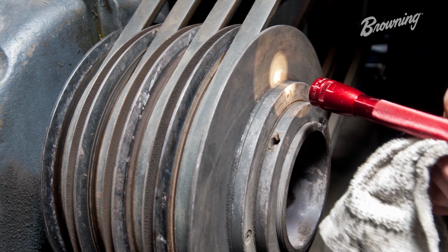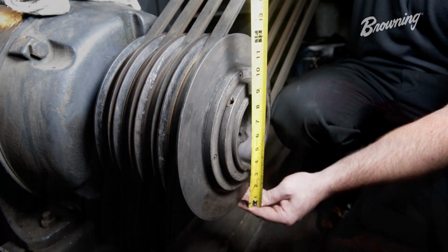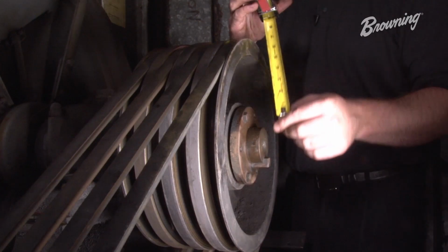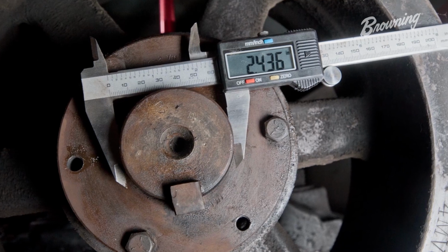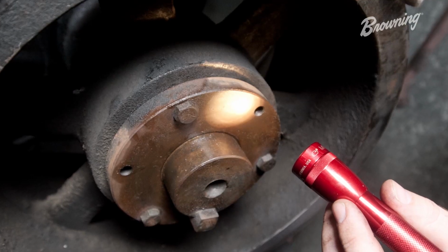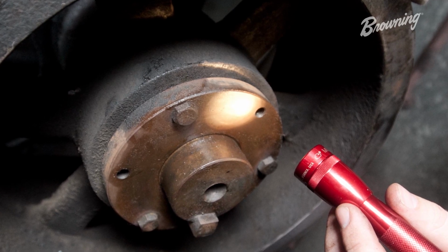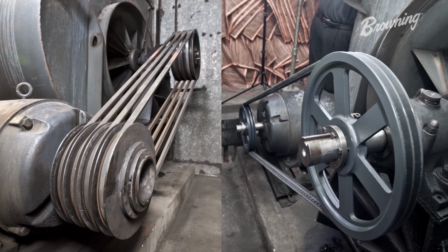Do your best to retrieve both the motor and fan sheave part numbers. If a part number cannot be found, then provide the outside diameter. Along with the outside diameter, we will need the number of grooves, the belt and bore size, whether or not a bushing is required, and finally, whether the sheaves are variable or fixed pitch.